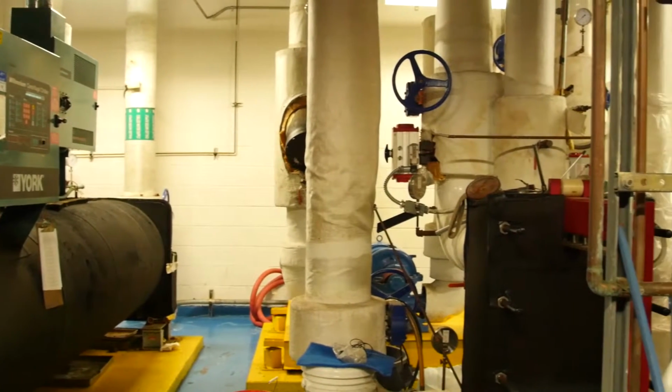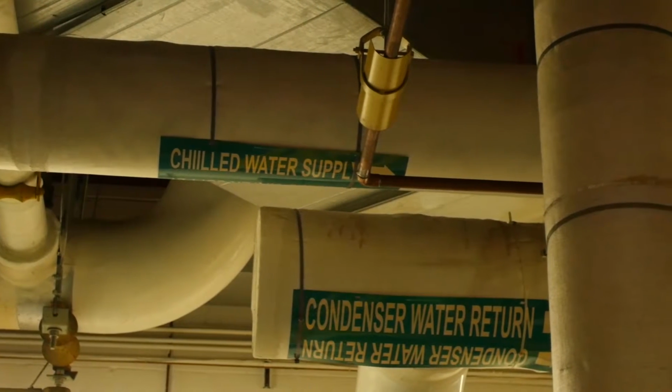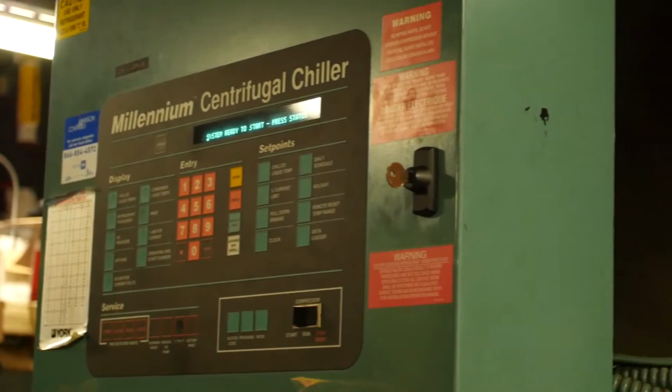So what happened was the Permafrost company comes with highly trained, highly skilled engineers. So these engineers come to the garden and they attached to about 6 different sites on the chiller to see what the efficiency readings were. But before they added the Permafrost, what they did is they tuned the chiller to its ultimate capacity with their experience and knowledge. So subsequently, they made improvements in the chiller. They made improvements in the condenser water temperature. They made the unit run exactly the very best that it could. Then they added the Permafrost. It took about an hour for the oil to siphon into the oil chamber. They closed everything up, they took their equipment off, and they went away for a month.